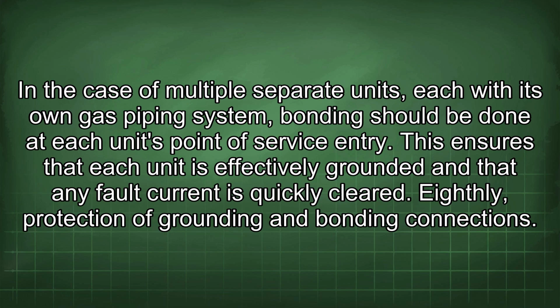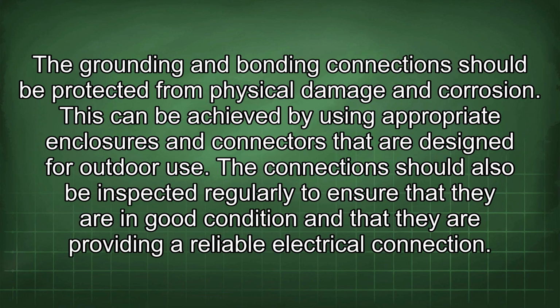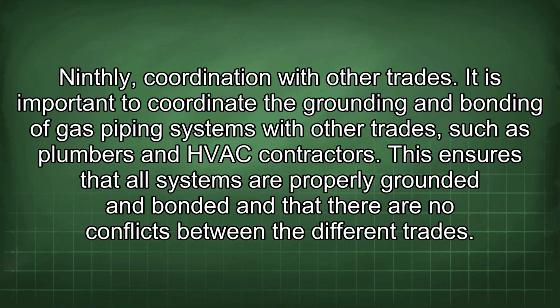Eighth, protection of grounding and bonding connections. The grounding and bonding connections should be protected from physical damage and corrosion. This can be achieved by using appropriate enclosures and connectors that are designed for outdoor use. The connections should also be inspected regularly to ensure that they are in good condition and that they are providing a reliable electrical connection.